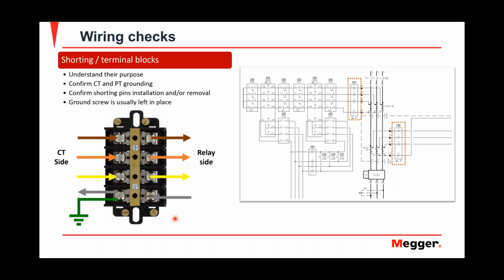Let's say you're at a site and you want to isolate the relay using the shorting block. Usually, the one that grounds this pin, it's left in there. Or at least that's my practice. That could change depending on the site. But usually, I leave that screw in because this is going to be the screw that's going to ground all the other currents. So we're going to go through the procedure. You put the first pin, which is the one that goes to the ground. Then you take another pin, you take it out of here and you put it in here, and then you short out your C-phase current.